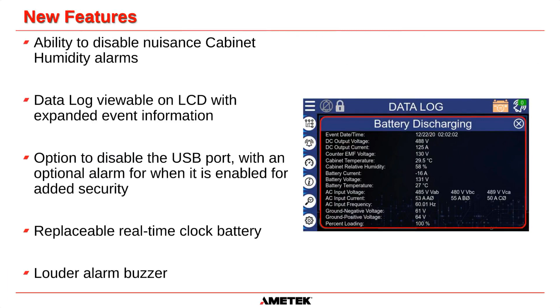Let me turn the whiteboard on again. You can see here that we have 106 amps flowing out of the charger, and that's flowing out to the load itself. If we showed the animated drawing, you would see that there was some current going to the battery, but the resolution on this current reading — the amount of current to keep a battery on float charge is usually less than half an amp. In truth, remember, this is a mock-up.